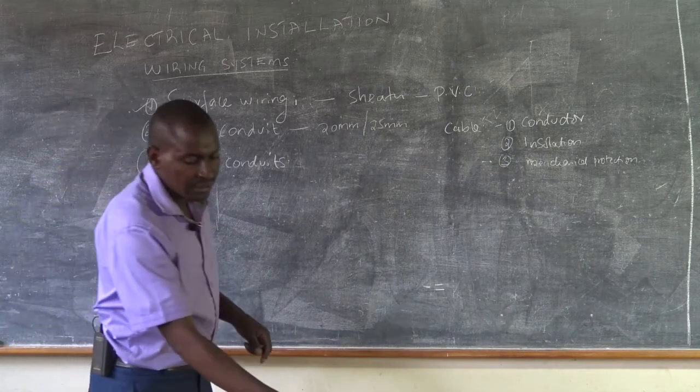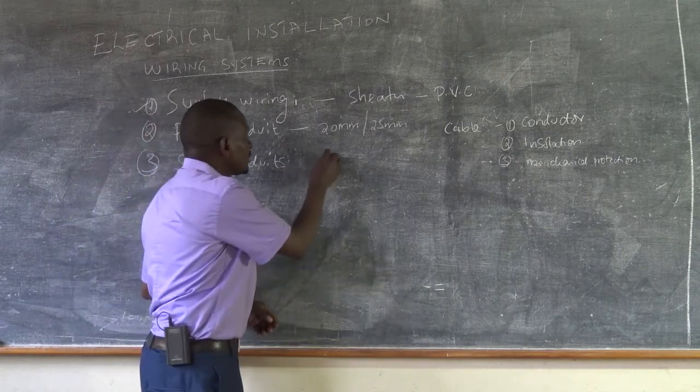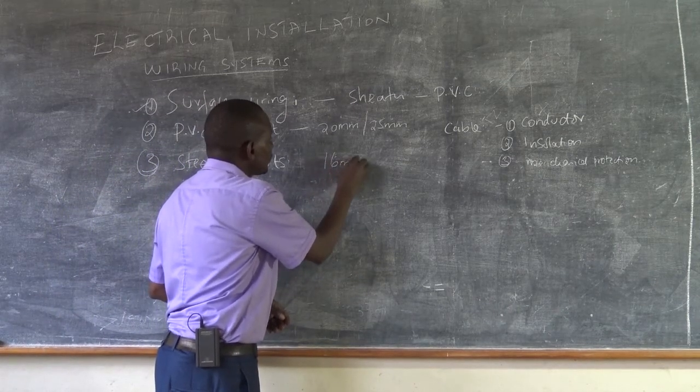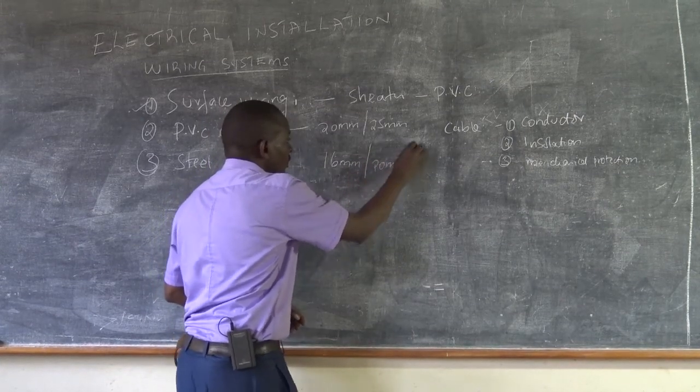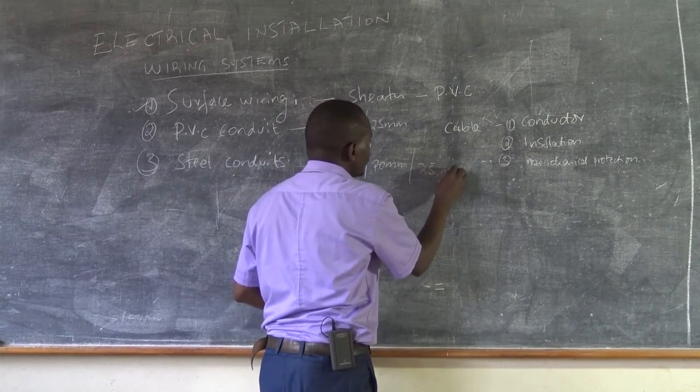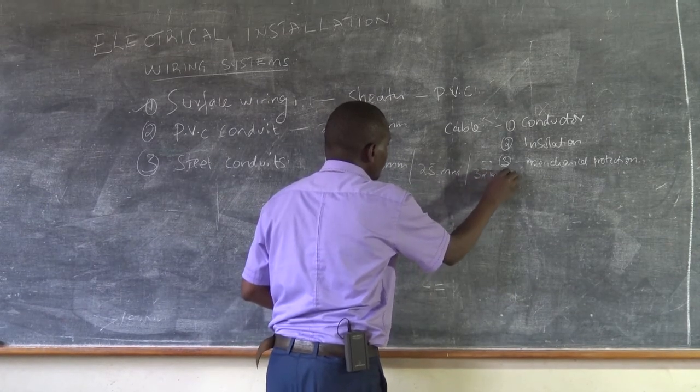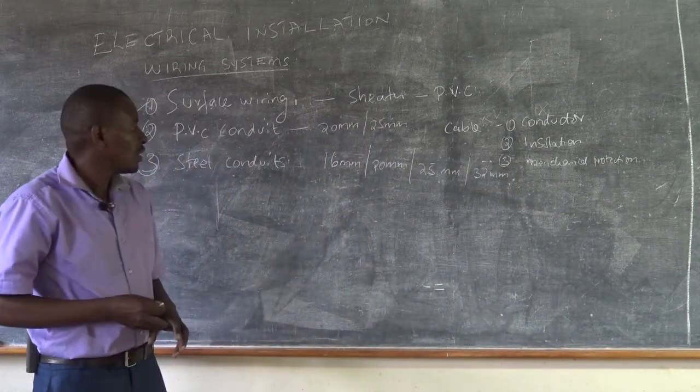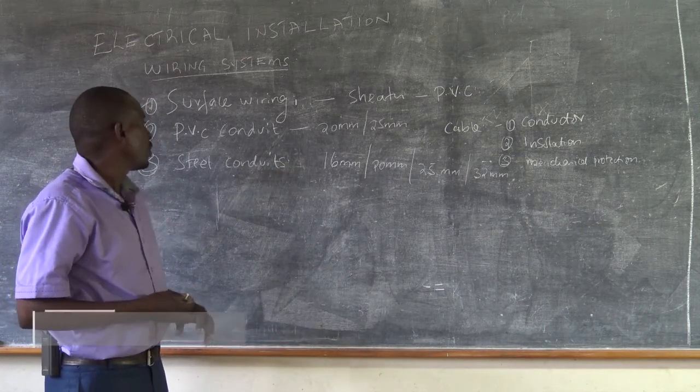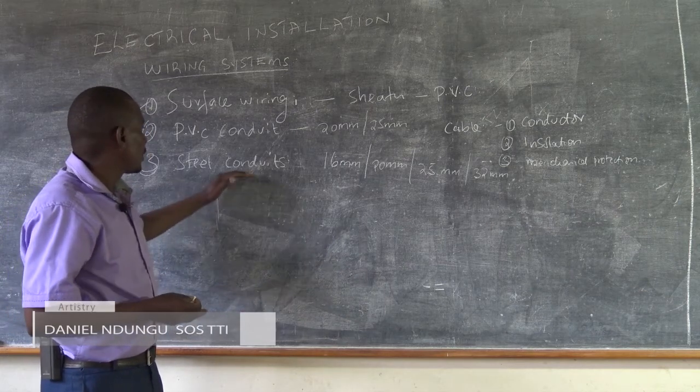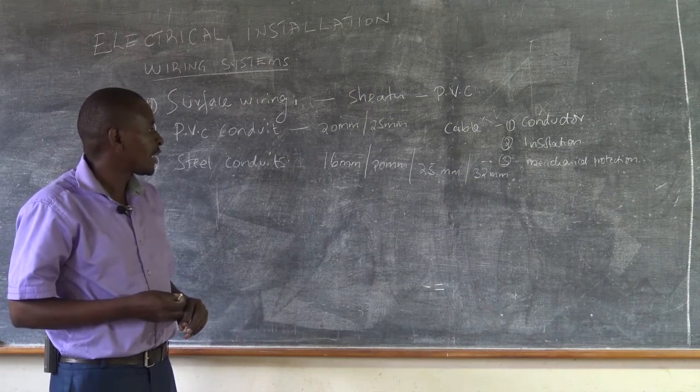Just as we have seen, the steel conduit also comes in sizes. We have one that is small, 16 millimeter. We have 20 millimeter. We have 25. And we have 32 millimeters. So that is the sizes that we have for conduit. We have the same for PVC conduit. But we are saying that steel conduit offers a better mechanical protection.